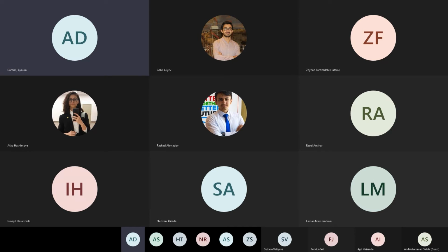Passive fire protection, in our case, we are just calling PFP. The goal of passive fire protection is to mitigate the effects of a fire, maintaining the integrity of critical structural components and of equipment containing hydrocarbons, and preventing their failure for a defined time as a result of high temperature caused by incident radiation or, in certain cases, jet fire impingement. Periodic inspection for damage and deterioration should ensure the continuance of adequate protection.